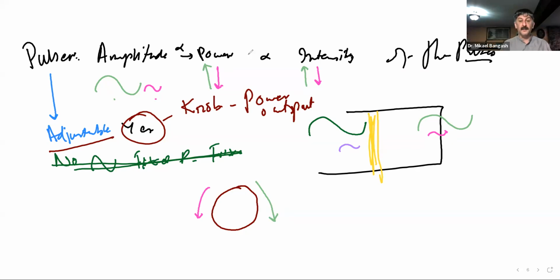But by telling the system, well, I'll convey the message to the pulse. I say, we want you to produce a wave with greater power, which will give it a greater intensity, which will cause the amplitude of the pulse, or the cycles in the pulse, to be greater. We do this by turning the power output knob clockwise. That sends the signal to the system, to the pulse, to send out a stronger electrical signal that will produce a sound wave with a greater amplitude of power.